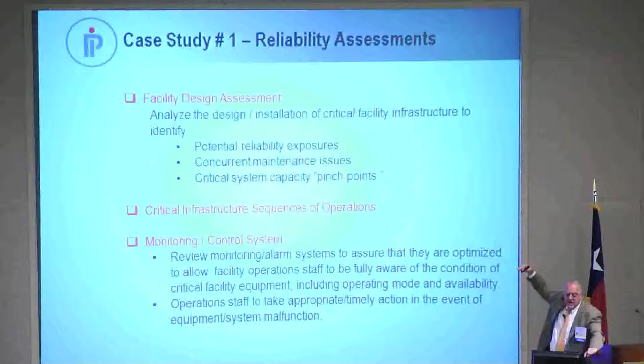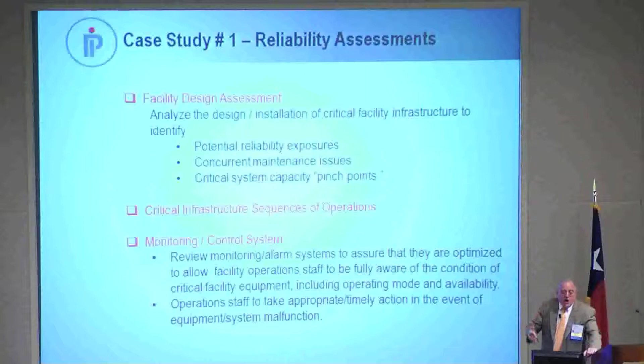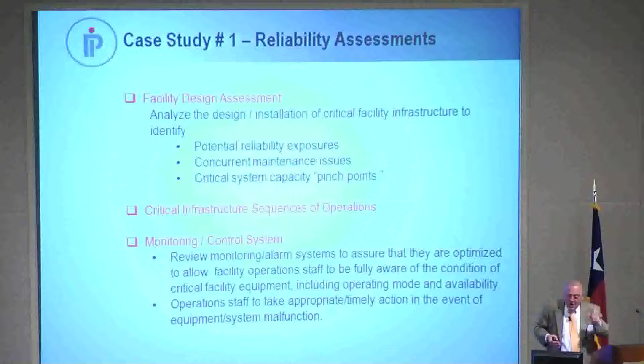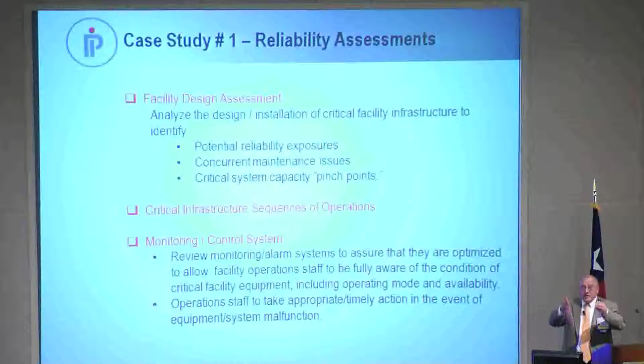So these facility assessments, or audits, are really put together to identify any potential reliability exposures you have within the facility. Are you running into any concurrent maintenance issues? And from a capacity standpoint, are there any pinch points? Am I exceeding my N+1 capacity? Do I not have enough cooling capacity on the data center floor?